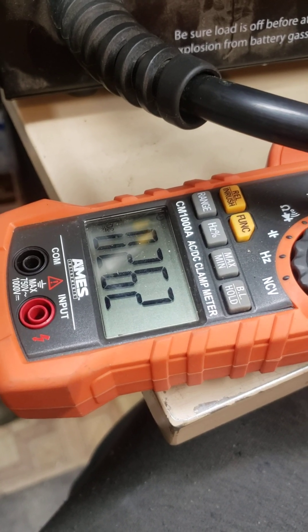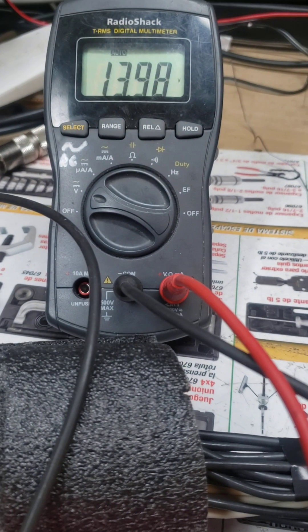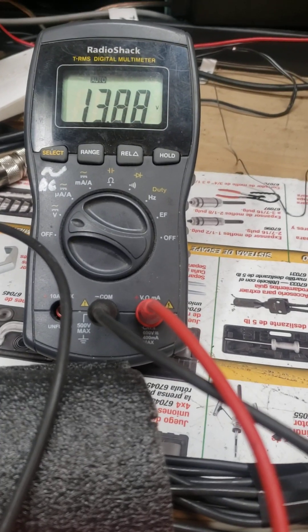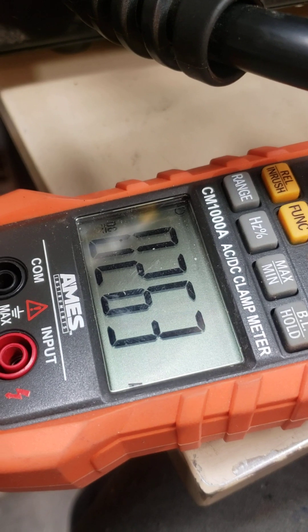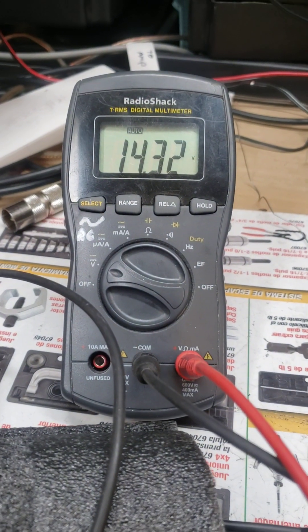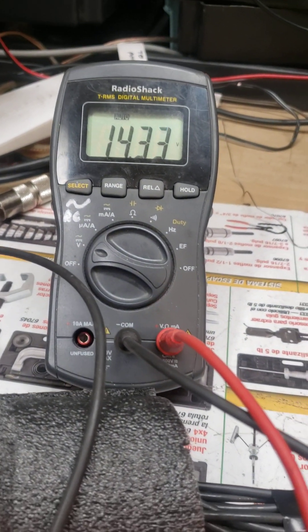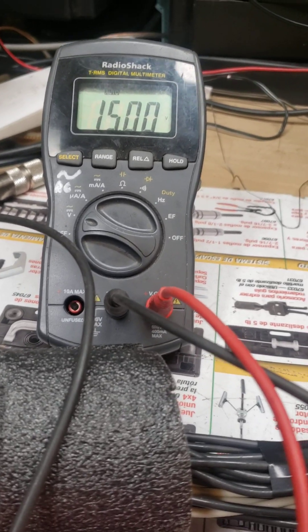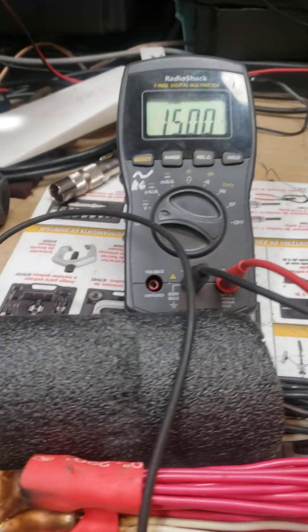This is 220 amps — that's 260 amps right there, 14 volts, dropping off pretty good. So 260 — let's see if we can round it out to 250. That's pretty close, 14.3 at 250 amps. Now we'll go kick on the load sharing and load it back down to 250.